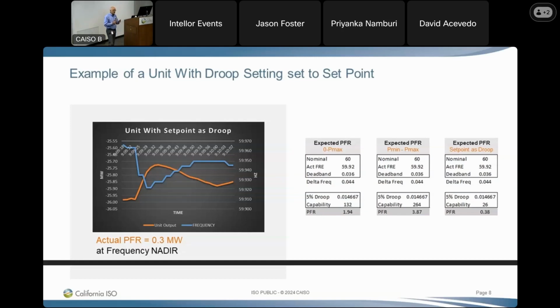We definitely are going to come after you if you've got your droop setting set to set point. And we're ramping up our process internally to get legal involved and to be able to come out and give you a warning, and then to say, if you're not doing things properly, this is what the next step is going to be. In this example, the unit is operating at -26 and it's charging at 26 megawatts. And the actual PFR they provided was 0.3 megawatts.